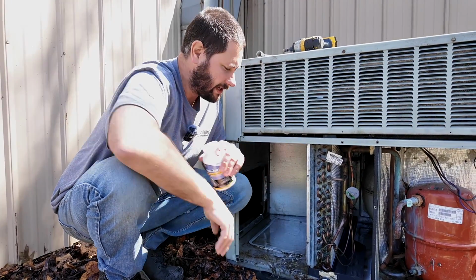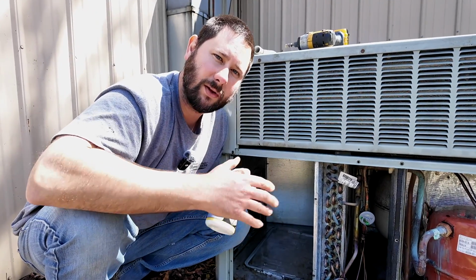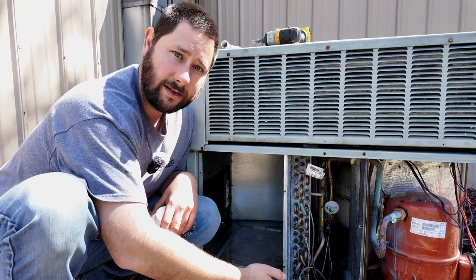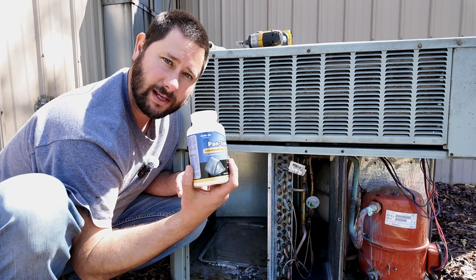Now, one thing I like to do is I like to treat the pan. These pan tablets will help to keep not only your drain clean, but it'll also keep your pan clean. So use this just to help with extra maintenance. When you perform maintenance, cleaning is part of what you need to do. You also need to check everything. You need to check the bearings on the motors. You need to check the charge and make sure the charge is correct. You need to make sure that you're checking the capacitors, the contactors, and other electrical components to make sure they're not faulty. That way you do not get a callback. The worst thing that you can get in the HVAC industry as a technician is a callback. So reduce your chances by making sure that you clean thoroughly and you check everything.